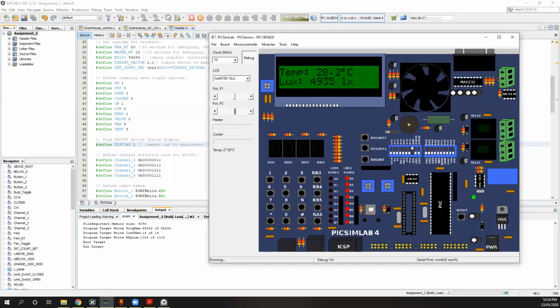The next thing we'll show you, I'll try it again with the temperature below 6 degrees, and then that should not activate the sprinkler. Before I go below 6 degrees, I would like to note that that will turn the buzzer on. The buzzer can be turned off by pressing the down button, or it will be turned off by returning to normal temperature, which is above 6 degrees. Okay, I'll show you that buzzer part first. As you can see there, it turned off when I pressed that button. It'll also turn off if I go above the 6 degree mark.